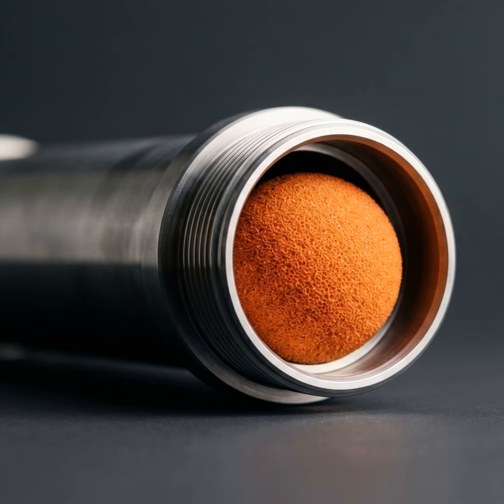So let me describe this for you because it's brilliant. Go for it. Instead of waiting for the mineral scale to build up over 6 months and then shutting the whole data center's cooling system down to pour acid into the pipes, the ATCS constantly circulates these small, soft, orange neoprene sponge balls through the titanium or copper condenser tubes. Orange sponge balls. Yes. And the crucial engineering detail here is that these spheres are slightly oversized compared to the precise diameter of the tubes.